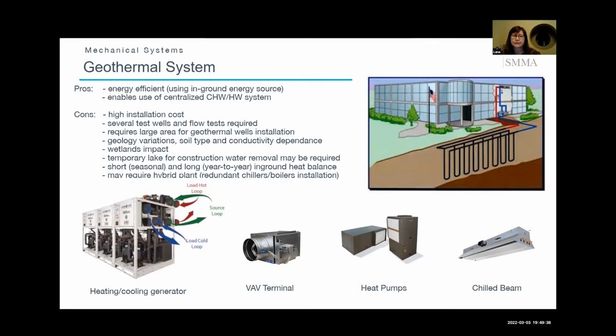As a result, these systems are usually designed with some extra wells drilled, and we also suggest providing either a provision or installation of redundant sources of cooling or heating. It could be a chiller, a cooling tower, or a boiler, just in case the well's production diminishes over time, so you have a source to support the system in the building.